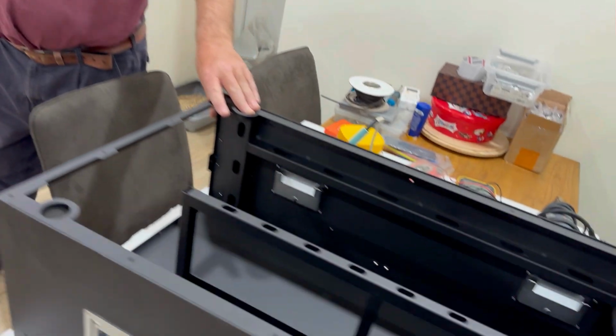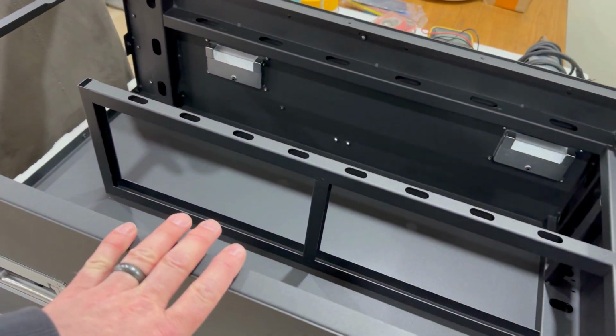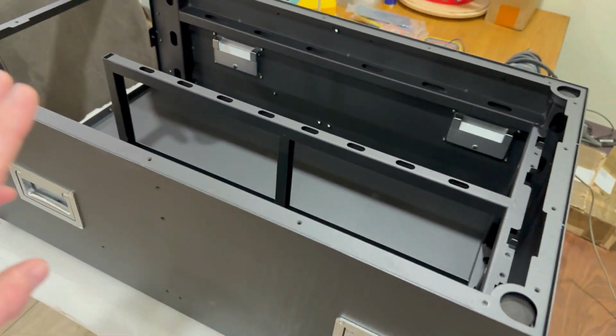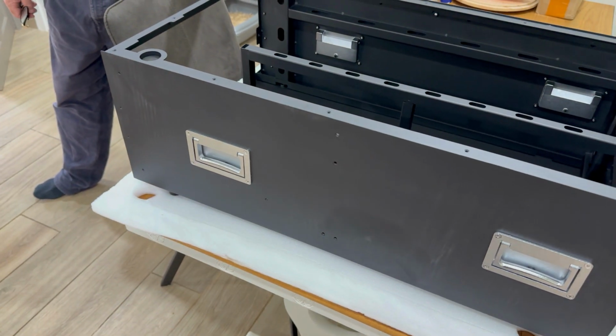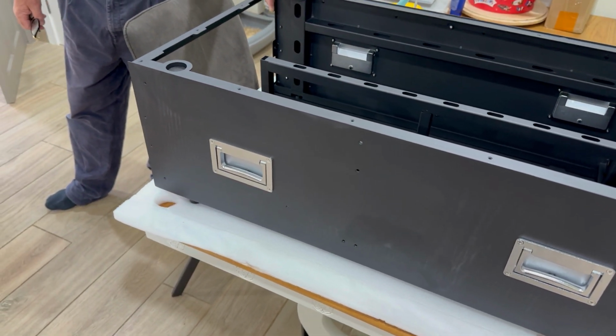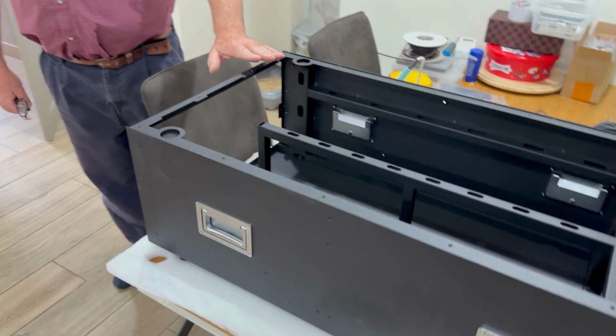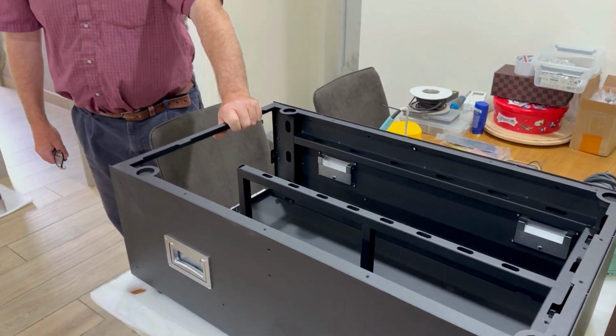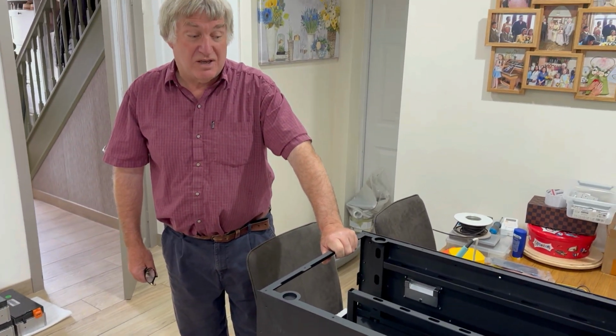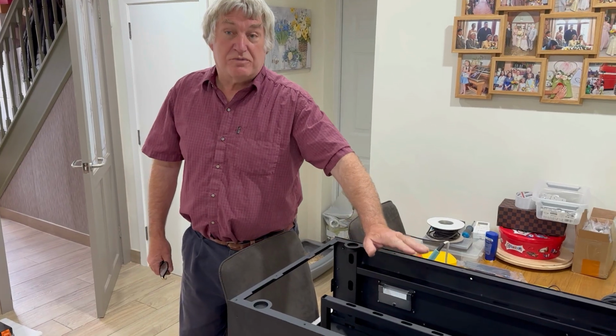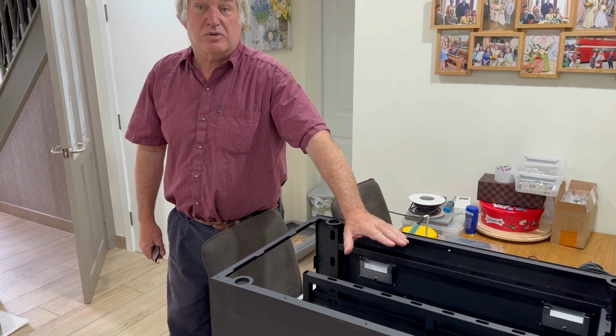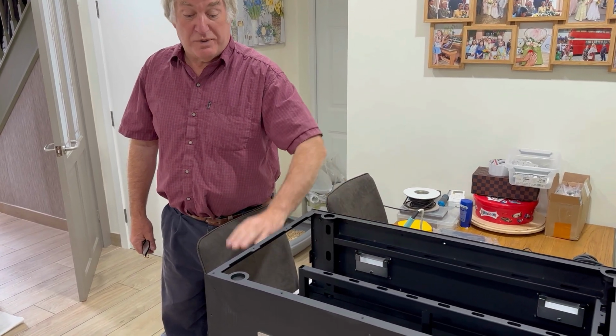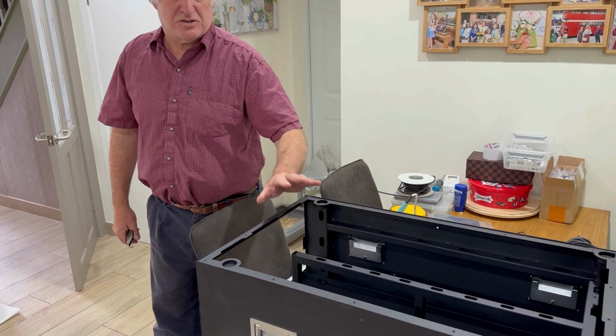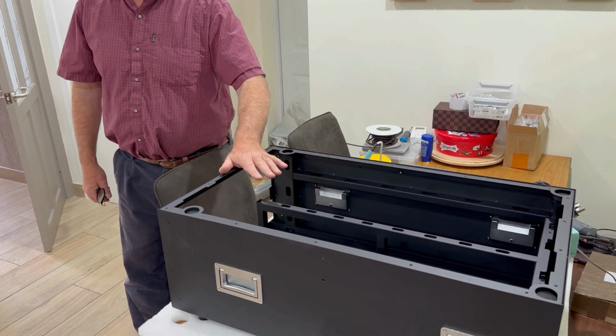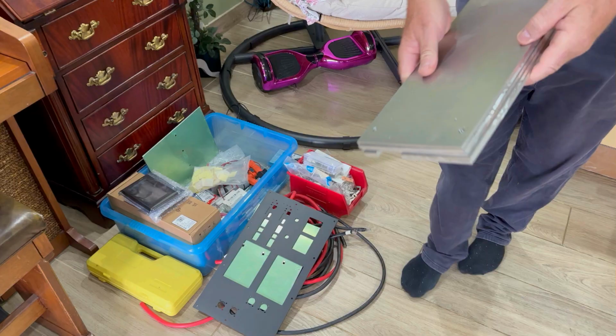So what we'll end up with in this box is essentially a bank of 2 individual batteries inside the one box. This will be a 10 kilowatt hour box in storage capacity. Inside there will be 2 5 kilowatt hour battery modules, and there'll be 2 BMSs. So basically this is 2 batteries in one box, purely just to use all the space.